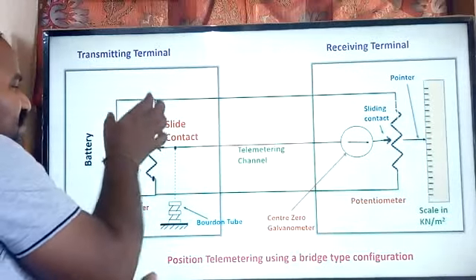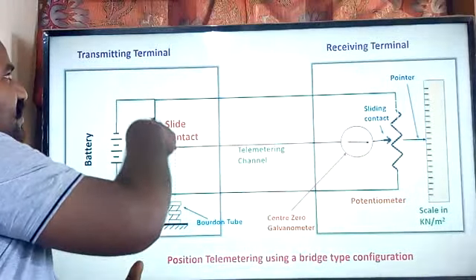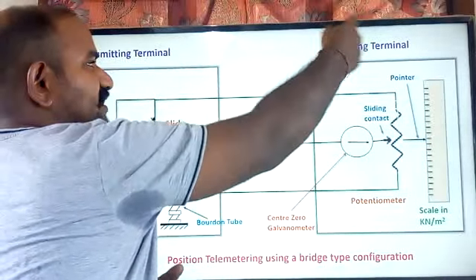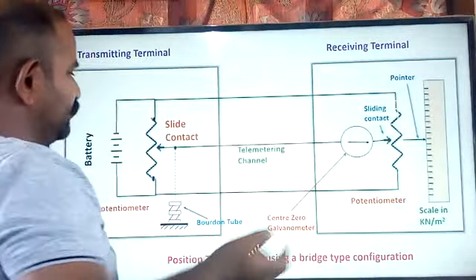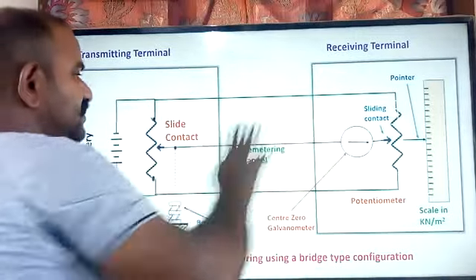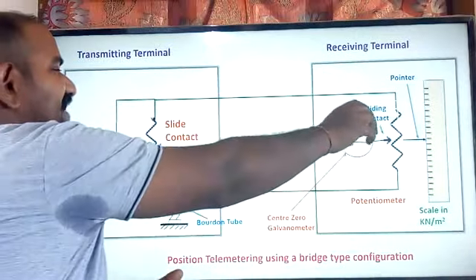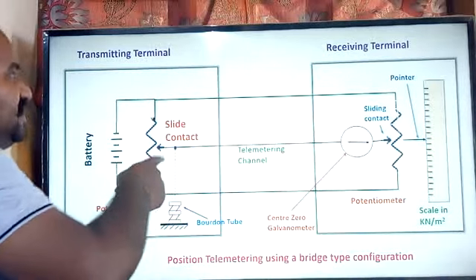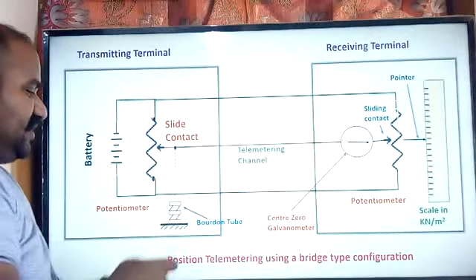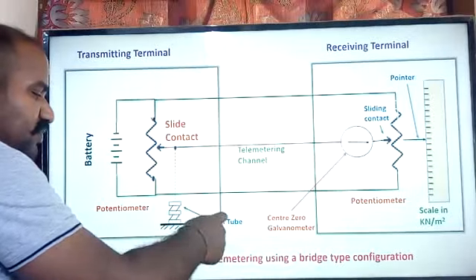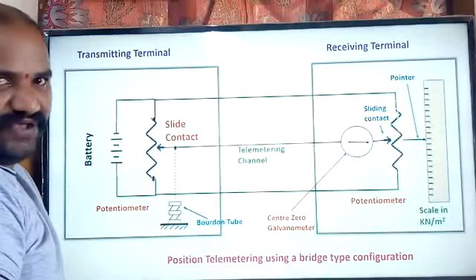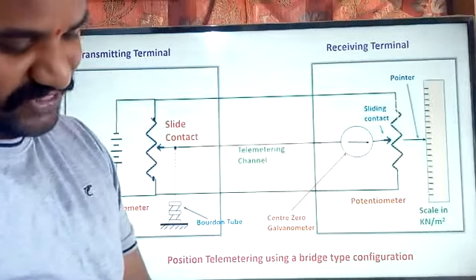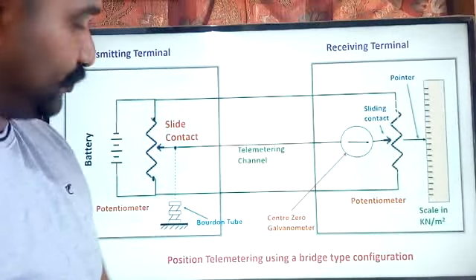The potentiometer at the transmitting end and the potentiometer at the receiving end have their sliding contact points in the same position. When there is a change at the transmitting end, we use a Bourdon tube to sense the pressure of a physical variable. The Bourdon tube is used as a sensor — that is, a transducer — and based on this transducer the sliding contact changes its position either upward or downward.